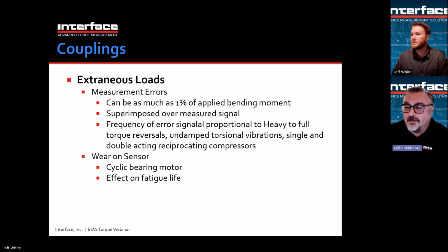On the other hand, a coupling does the same thing, but with a very soft element in the middle, such that the shafts are not bent into alignment. The errors due to, say, bending loads are superimposed over the measured signal. So you have a torque and a signal due to that torque, but you also have an error signal that is superimposed on the torque signal. The frequency of the error signal would be proportional to RPM. So basically you might have one cycle of the error signal per every rotation of the shaft. And as it rotates 1,000 times a minute, you'll have a 1,000 per minute error component that you can filter out. But if you're trying to look at dynamic torque, you may not want to apply such a heavy filter.